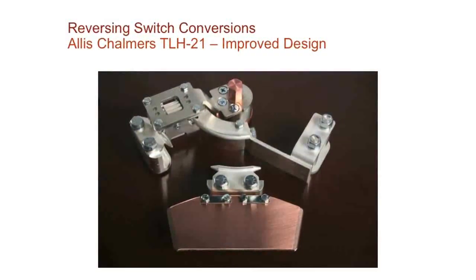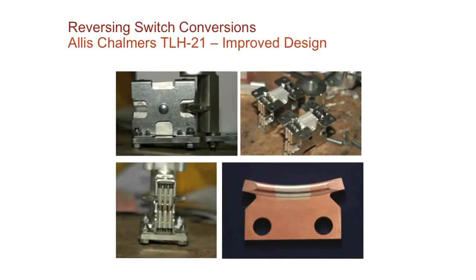This just shows you a breakdown of the different component parts. Talked a little bit about a silver inlay in the contact parts. What that does is that keeps the temperature down on the contact surface. So what that allows us is once you get the temperature down, then you have a better scenario to not create the carbon oxide that we were talking about when we were talking about the oil sampling and stuff. So it's just another advanced method that we have today that was not necessarily going on. Talked about the selector switch, the moving contact, finger assembly, and the stationary contact is a tungsten type contact as well.